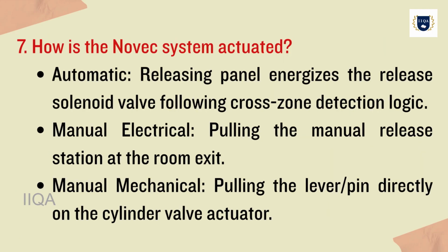7. How is the Novec system actuated? Automatic: the releasing panel energizes the release solenoid valve following cross-zone detection logic. Manual electrical: pulling the manual release station at the room exit. Manual mechanical: pulling the lever pin directly on the cylinder valve actuator.